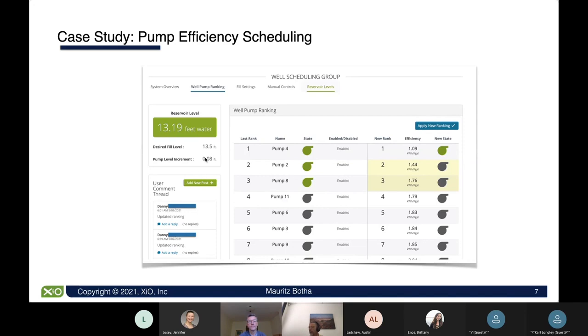Based on the pump level increment derived from demand, we only need to run 3 of these pumps. The ranking was based on the energy efficiency calculations from the previous day. So based on these values, that is how we schedule these pumps so that they always run the most efficient pump first.